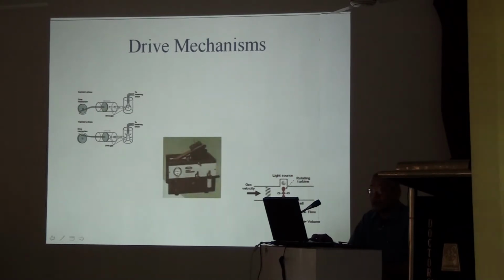Then another variety is spring loaded or weighted. There is a weight inside over the thing and a spring inside. So, counteracting the forces of the spring and the weight, the ventilator operates.